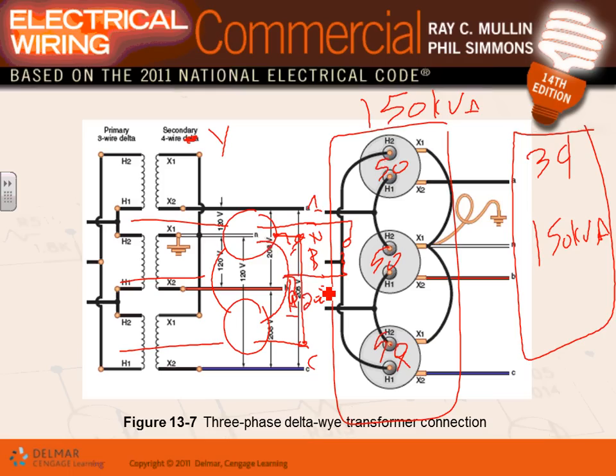90% of the time. On that center tap delta, isn't there some kind of configuration that causes you... Don't they have to warn you that there's two phases that if you put them together, you end up with like 208? Yes, they have a wild leg, phase B, typically the wild leg, labeled orange. And they have to warn you on the panel that says wild leg, high voltage to ground is 208. What questions though? I think it appears in the chapter in the industrial. It's not straightforward. And that's what we're going to be doing.